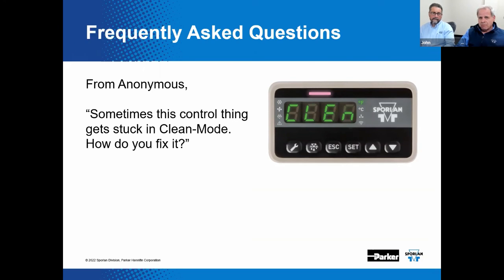Okay, in clean mode, the valves are shut. So they are closed and the fans are turned off. So that is a way to shut things down to effectively clean the case. All right. Hence the name clean mode. Now that might also happen, I think, if a refrigerant leak is detected or something of that. It could. That could happen. And so it gets stuck in clean mode. So how do you unstuck it?